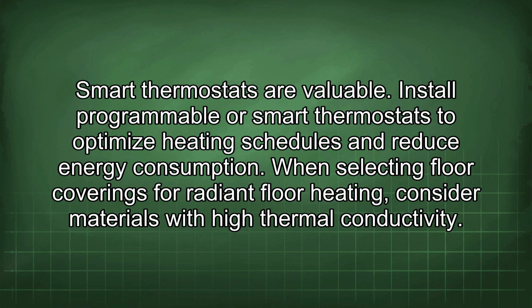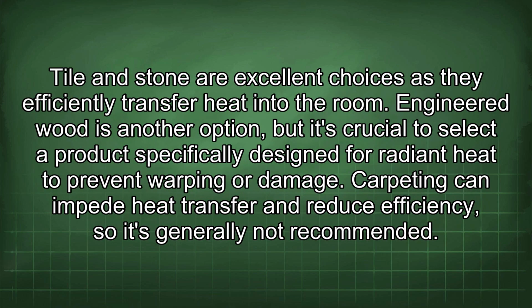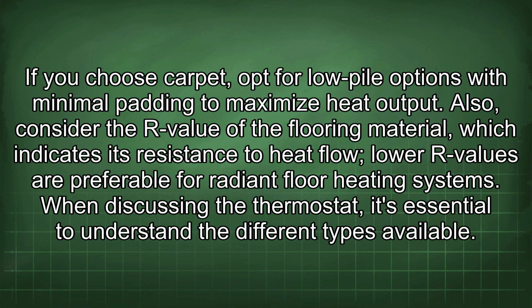When selecting floor coverings for radiant floor heating, consider materials with high thermal conductivity. Tile and stone are excellent choices as they efficiently transfer heat into the room. Engineered wood is another option, but it's crucial to select a product specifically designed for radiant heat to prevent warping or damage. Carpeting can impede heat transfer and reduce efficiency, so it's generally not recommended. If you choose carpet, opt for low-pile options with minimal padding to maximize heat output.